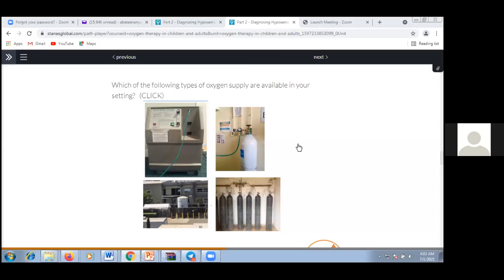Thank you. Very good. So that means the place you are working, St. Peter, is planning to have an oxygen producing plant. No, it's from a central source. Yes, a central source pipeline, an intra-hospital oxygen pipeline distribution network.